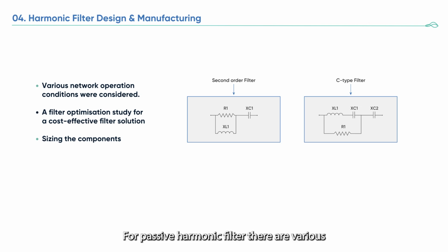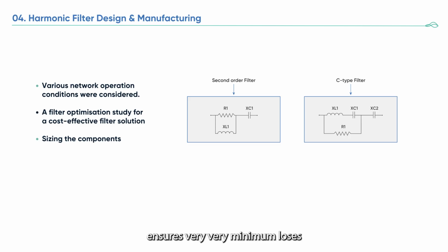For passive harmonic filter, there are various options, but for this particular application, two types were applicable. One of them is second order filter, the other one is C-type filter. Only difference between these two filters is the capacitor here, which is called the auxiliary capacitor, mainly at 50 Hertz. C-type filter ensures very, very minimal losses. Based upon nominal parameters of the filter, there will be no losses, but of course in real life the components will have some tolerance and there will be some loss, but the losses of C-type filters are very, very minimal. So the C-type filter ensures a cost-effective design in the long term.